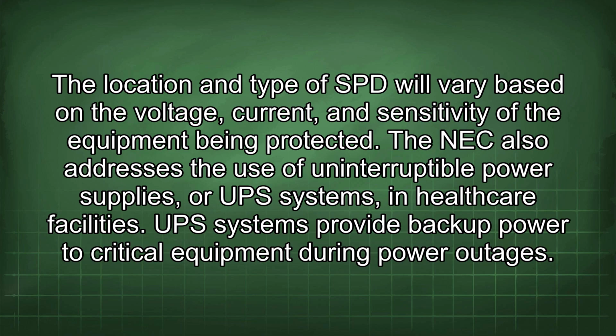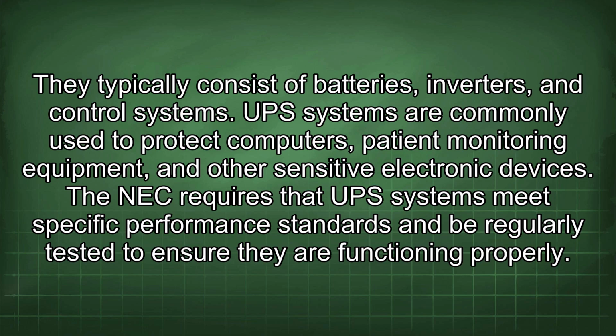The NEC also addresses the use of uninterruptible power supplies, or UPS systems, in healthcare facilities. UPS systems provide backup power to critical equipment during power outages. They typically consist of batteries, inverters, and control systems. UPS systems are commonly used to protect computers, patient monitoring equipment, and other sensitive electronic devices. The NEC requires that UPS systems meet specific performance standards and be regularly tested to ensure they are functioning properly.